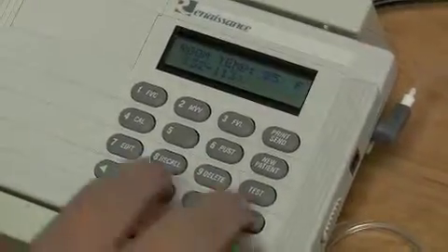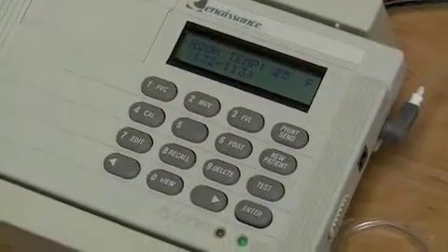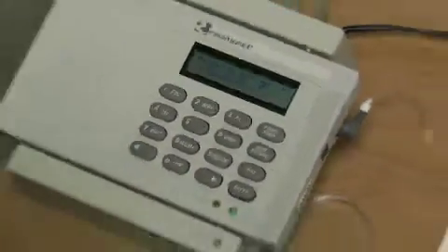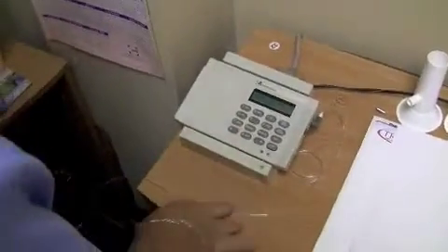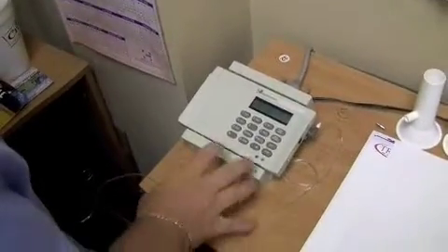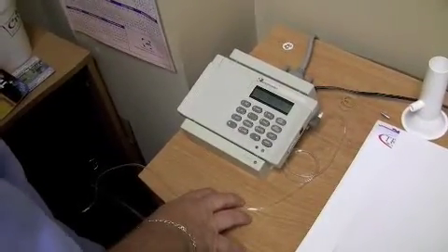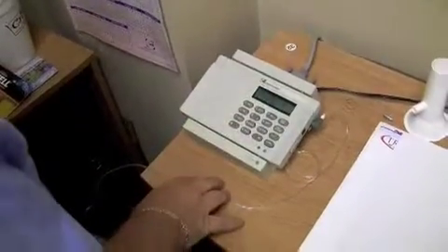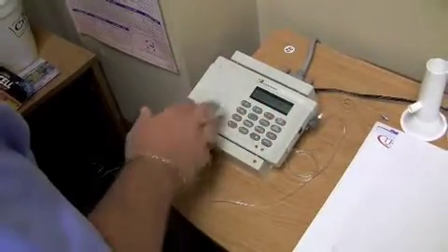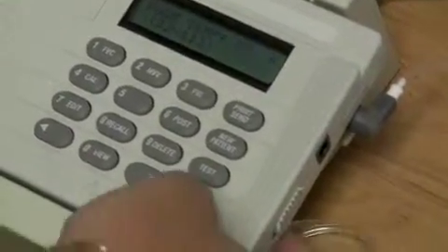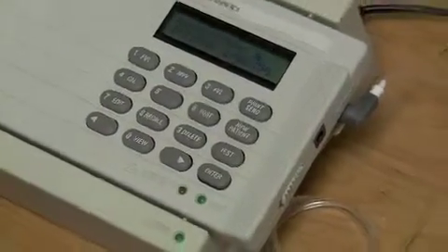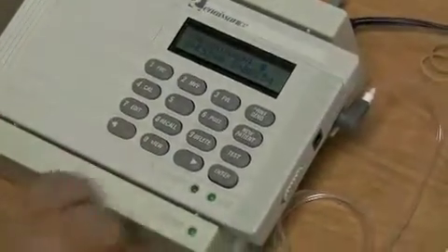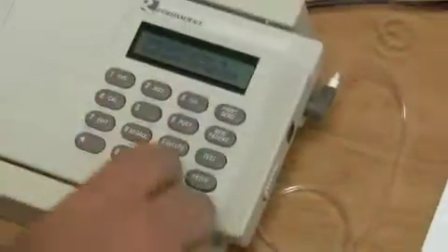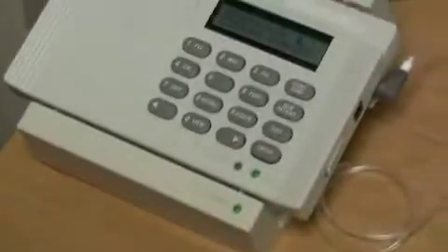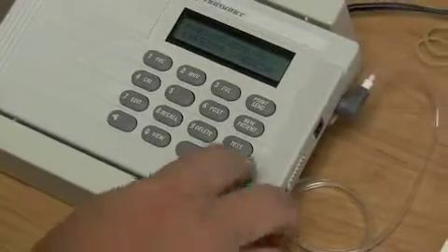This is very important, the next step, the room temperature, because it's going to make the adjustments according to the room temperature. We keep our rooms around 75 degrees, but make sure you always check the temperature on a thermostat to make sure that you have the proper setting in here. If it was 77, simply push in 77 and enter. Once that's done and you feel good about the temperature, push enter. The pneumotach will always be 1. You push that. It says which pneumotach, basically which model, and ours is model 1. Right, model 1, and then enter.